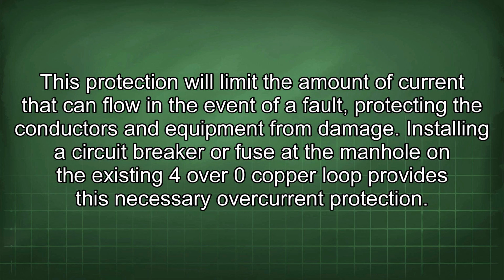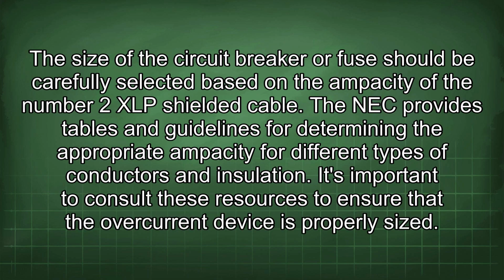Installing a circuit breaker or fuse at the manhole on the existing 4/0 copper loop provides this necessary overcurrent protection. The size of the circuit breaker or fuse should be carefully selected based on the ampacity of the number 2 XLP shielded cable. The NEC provides tables and guidelines for determining the appropriate ampacity for different types of conductors and insulation. It's important to consult these resources to ensure that the overcurrent device is properly sized.